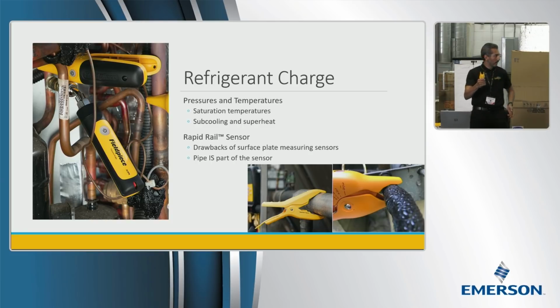So why is that useful? Well, what a rapid rail sensor does is use the conductive properties of a copper pipe to close the thermocouple circuit, and the pipe becomes part of the sensor. So no longer is it a sensor on top of a pipe measuring surface temperature. The pipe becomes part of the thermal sensor here. So you get an accurate reading instantly when you're measuring a pipe temperature. What this requires is at least 1 point of connection onto a pipe.